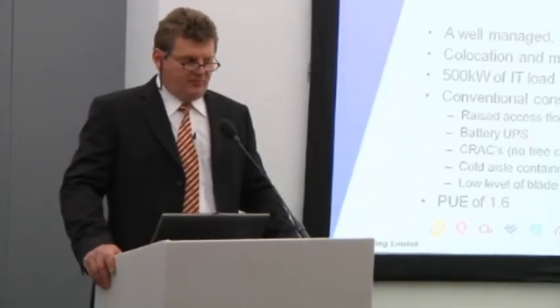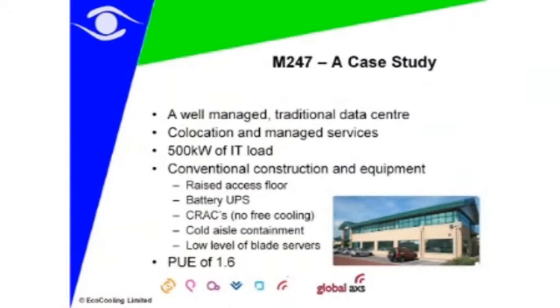The company I'm going to talk about is M247, up in Manchester. The reason I'm going to talk about M247 is it's a very professional, well-organized, traditional data center with conventional equipment, and they were looking for a retrofit solution with nothing too complicated or too bespoke. They've got 500 kilowatts of load, a conventional raised access floor, conventional CRACs, and conventional racks.